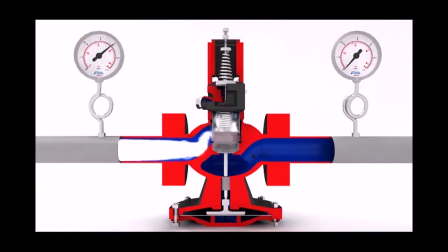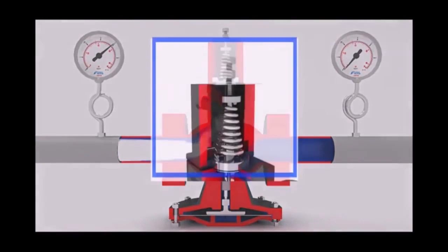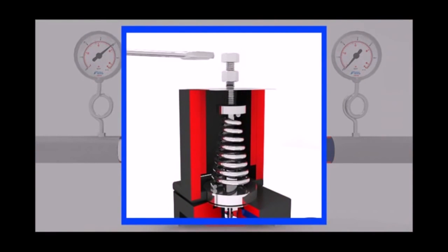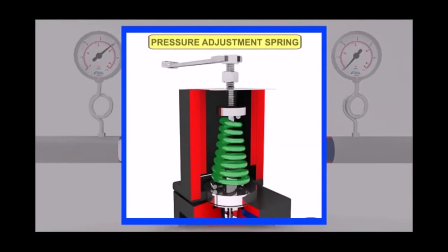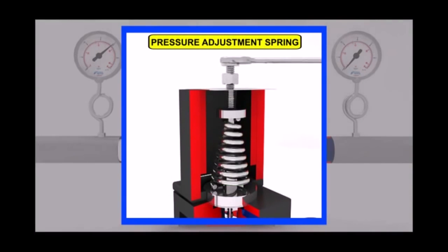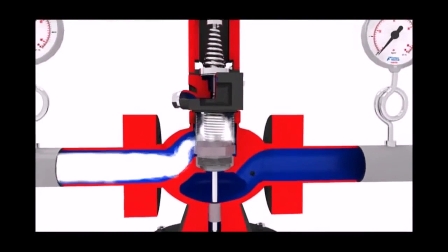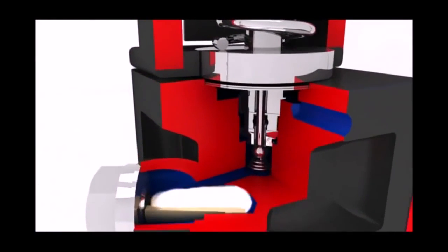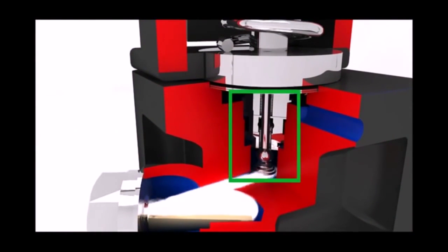and steam remains accumulated in the main valve chamber. Tightening the pressure adjustment bolt compresses the pressure adjustment spring. This results in deformation of the pilot diaphragms, which in turn pushes the pilot valve plunger and SS ball against the spring located below, causing the pilot valve to open.